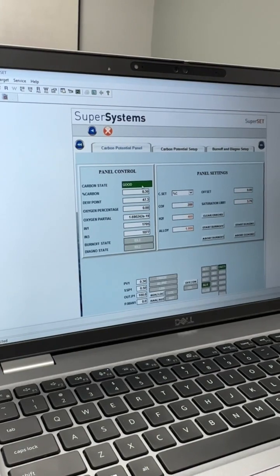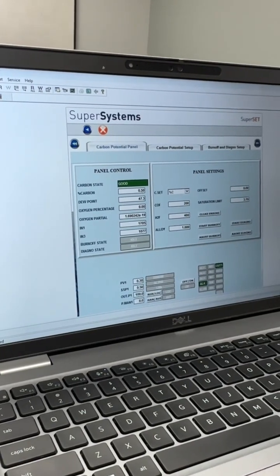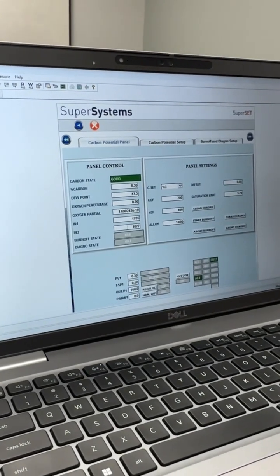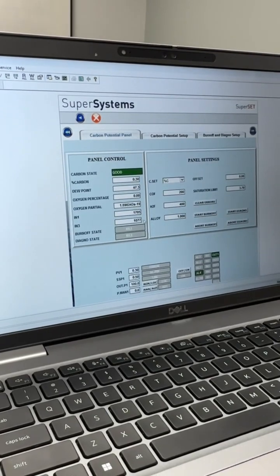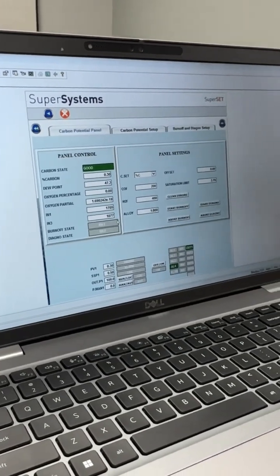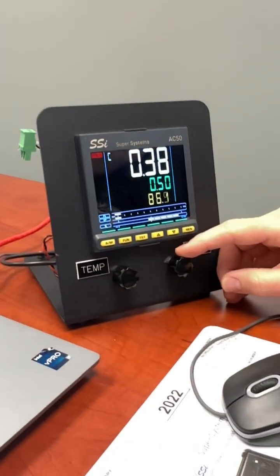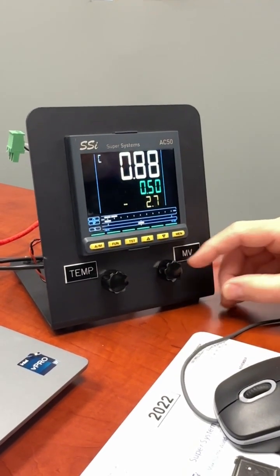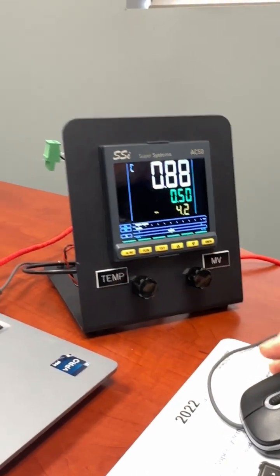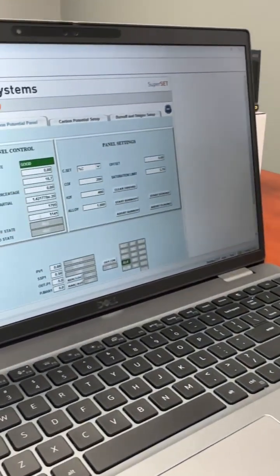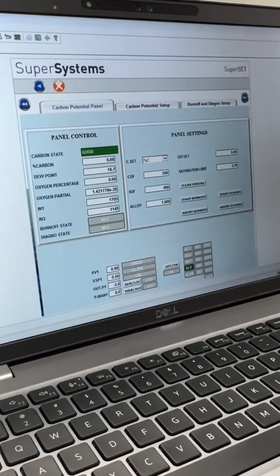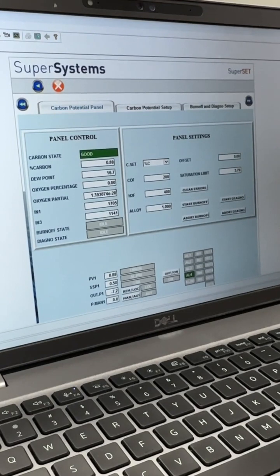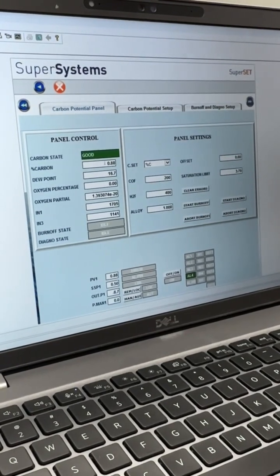Here we can currently see we have a good carbon state, and below we can see that our input three probe millivolts is 1077. If an adjustment was to be made at the instrument and the millivolts were to increase, we can see on our Superset software that input three did actually increase up to 1141, and our carbon potential is reflecting the new calculated carbon.